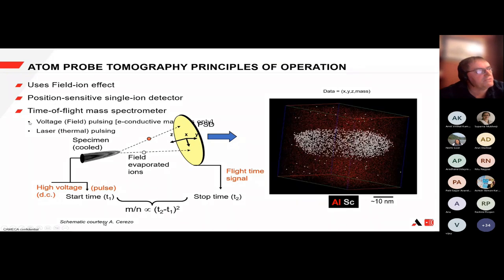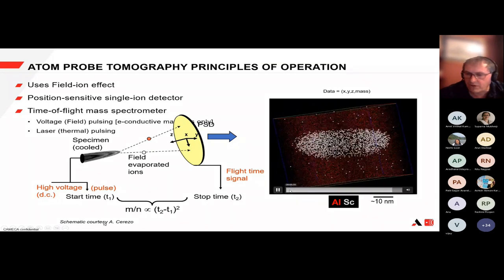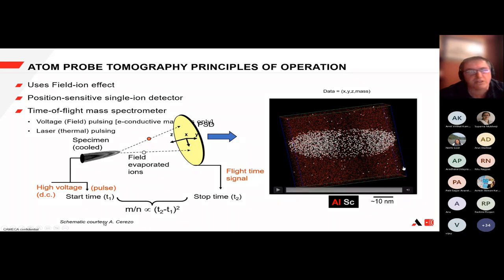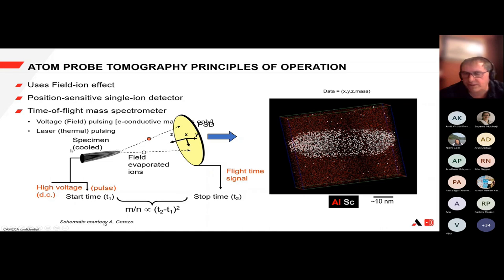The atom probe uses a DC field and a pulsing technique to allow time-of-flight measurements, measuring the time it takes for individual ions to leave the specimen and arrive at the detector. We get a mass spectrum, allocate mass-to-charge to each peak, and identify the ions. This is done at UHV, and we keep the specimen cold during the experiment to preserve spatial resolution, suppress migration, and minimize the thermal energy of the departing ion species.